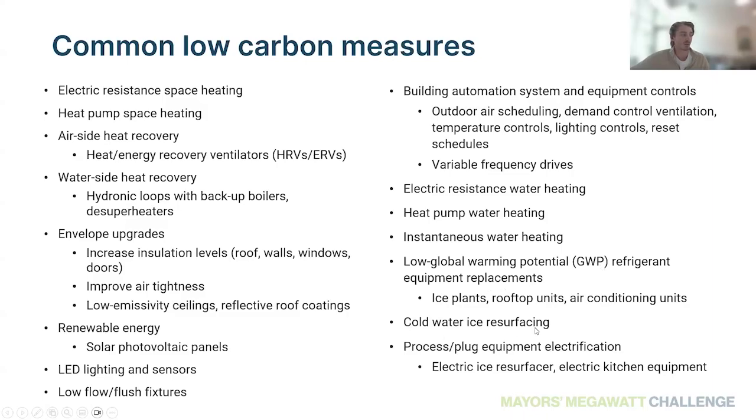Cold water ice resurfacing for arenas. So the reason floodwater is heated is to degas the floodwater before it's added to the ice to make for a stronger connection to the ice. Cold water ice resurfacing, instead of using temperature to do so, you use pressure. So you're using less fuel to heat the floodwater. You're adding less heat to the ice surface. If you have it, there's obviously less hot water being added, so less moisture in the space, less evaporation. So if you have a dehumidifier, you're reducing the load on that. If you don't have a dehumidifier, you're reducing the moisture issues in the space.